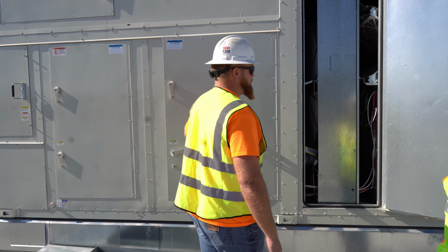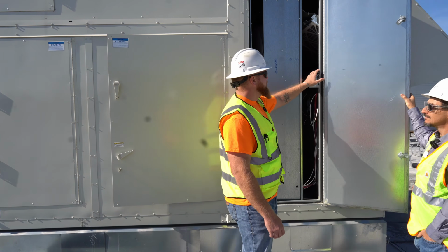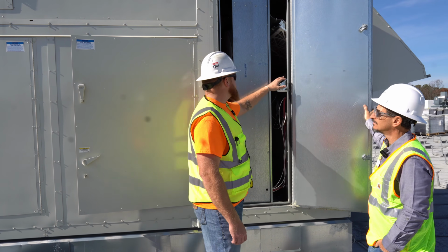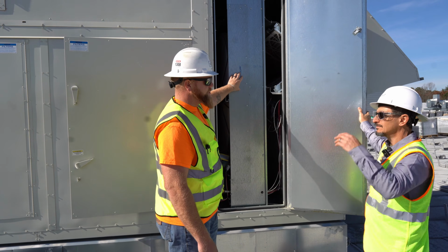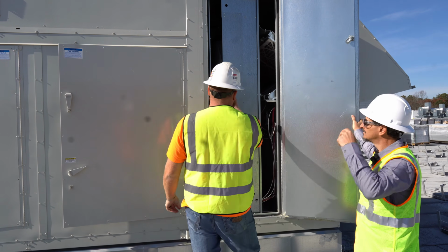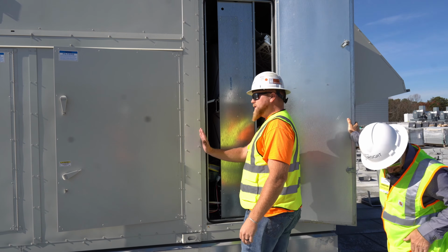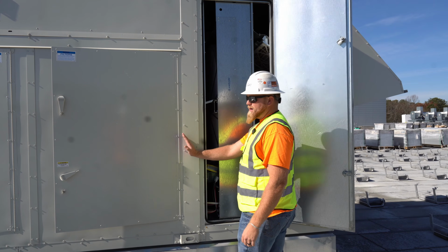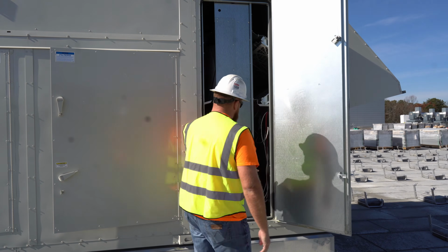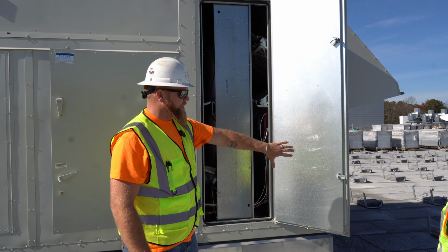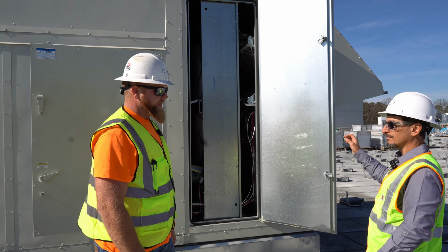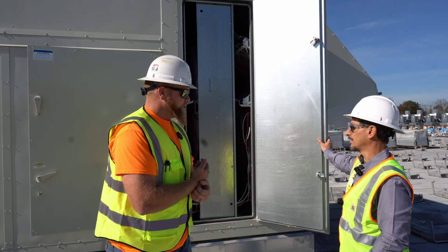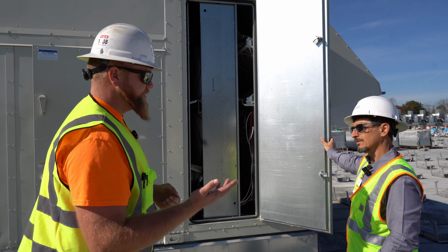We do have differential pressures to monitor filters. So we have outside air pre-filters. We do not measure the differential pressure on the wheel. Post wheel, final filters will be monitoring the exhaust return. Then to the final piece, when they put the exhaust dampers out here, we'll be monitoring the exhaust duct static, to be able to control space pressurization with the exhaust fan.